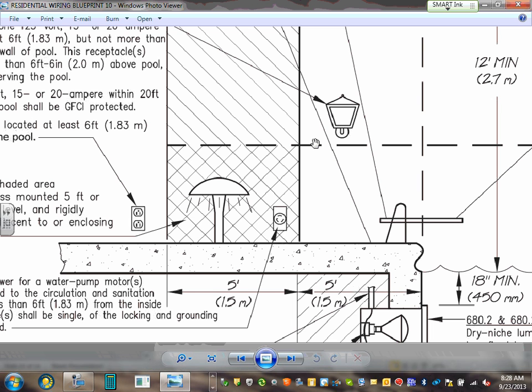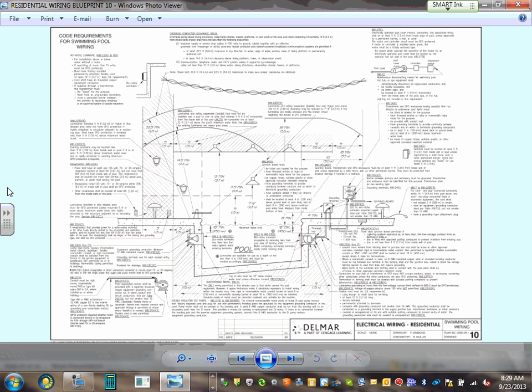What else? The pumps themselves, if they are 120 to 240 single phase, 15 and 20 amp, have to be GFCI. And there are a few rules about the heaters and so forth. Is this enough, guys, to get you up and running designing our swimming pool? For our system, I want you to show at least one receptacle with the rules for the receptacle, one switch, a couple of lights, wet or dry niche luminaires, and you also need to show a heater, because we have a water heater and a pump.